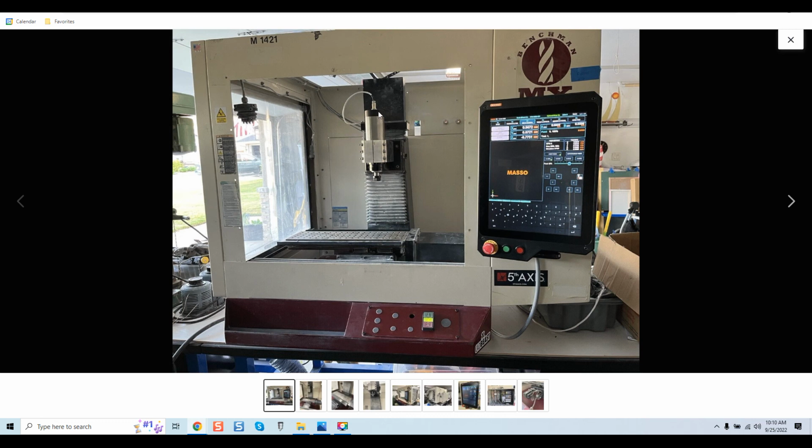Where it does become a big deal, if we look at this cable we see before us, this is a single-shielded cable. I'm assuming it's one that came bundled with the spindle. Why? There is no reason to use a single shielded cable because we know in best practice it should be using a double shielded cable to mitigate both frequencies of EMI, and of course the spindle outputs the largest amount of EMI on any system. This defines that the end user obviously does not know what he's actually selling. I'm sorry, there's no other way to put it.